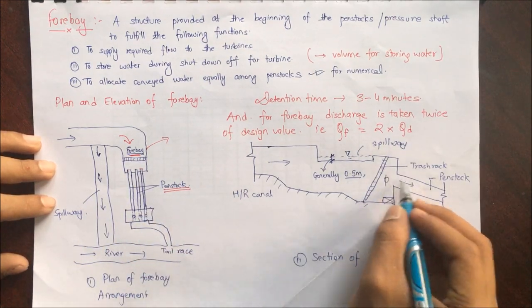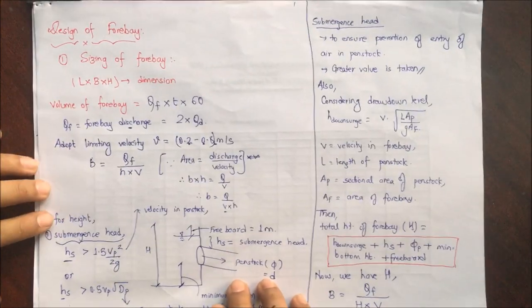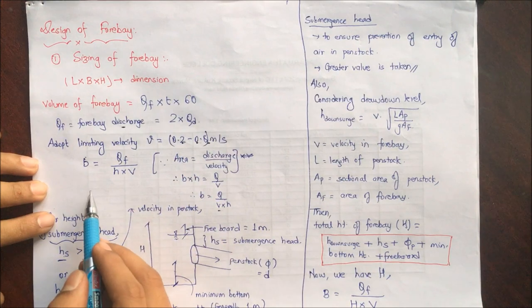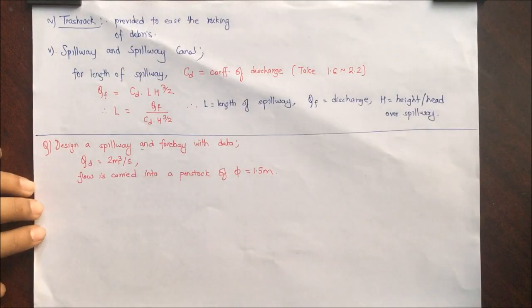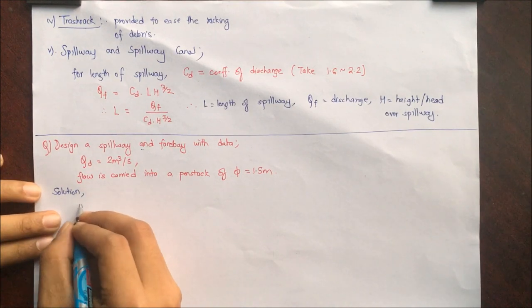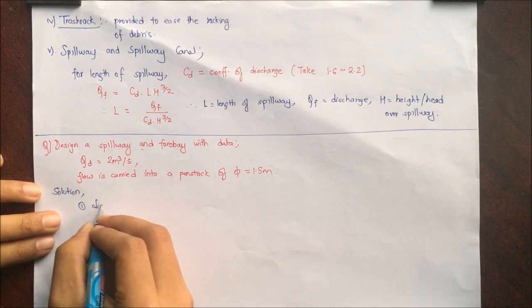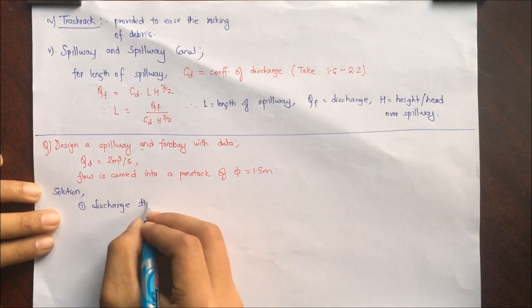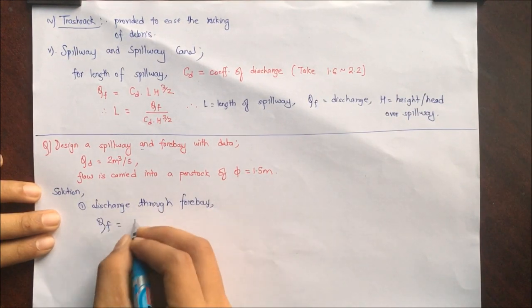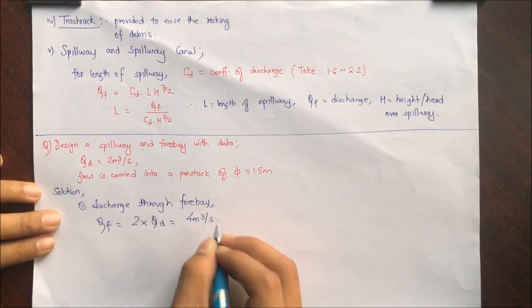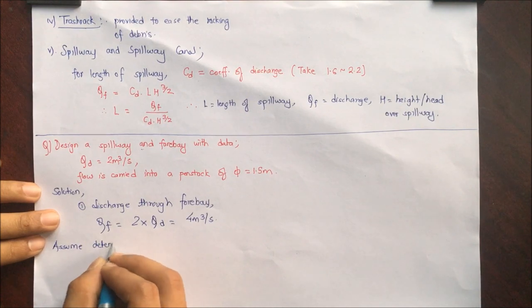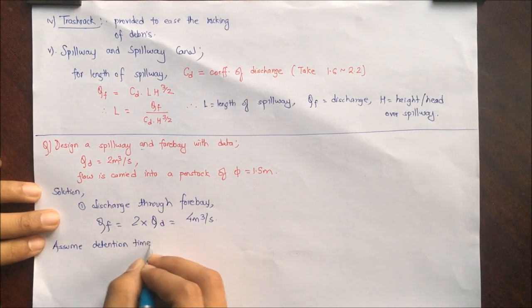The diameter has been provided, so these are the steps. As we know, sizing of forebay: Qf is equal to forebay discharge, that is 2 times of design discharge. The very first step we will be calculating is the discharge through the forebay: Qf = 2 × Qd, which comes as 4 meter cube per second. The question hasn't provided the detention time, so assuming detention time T = 3 minutes.